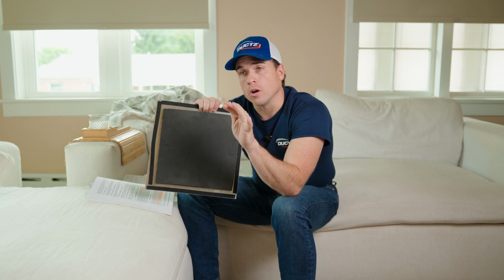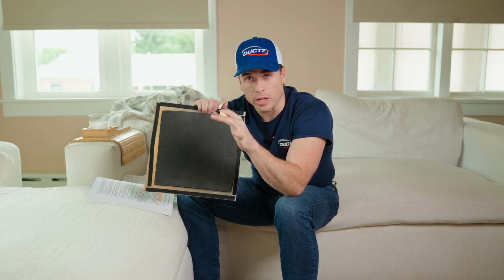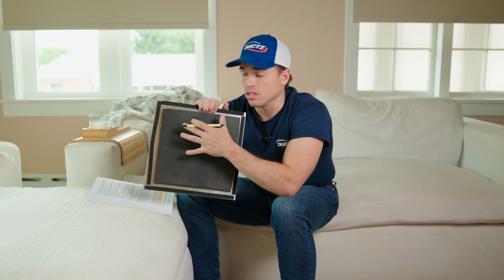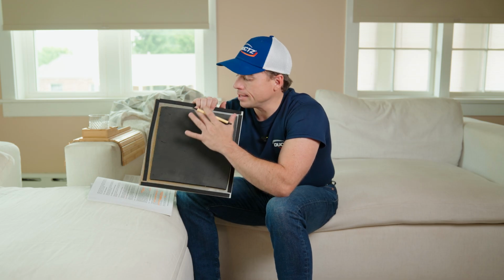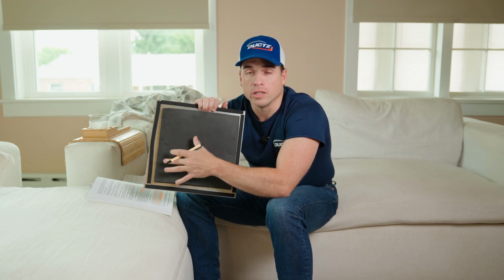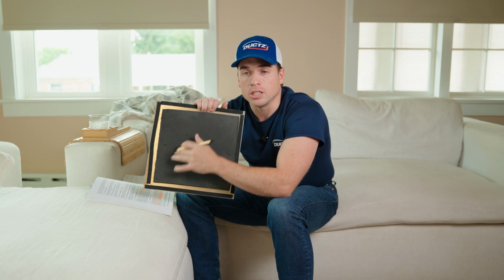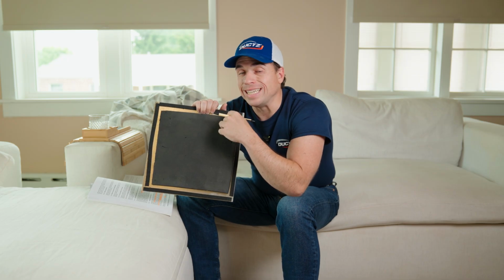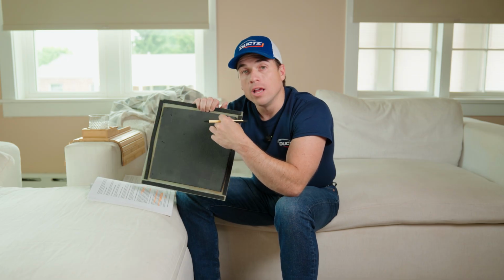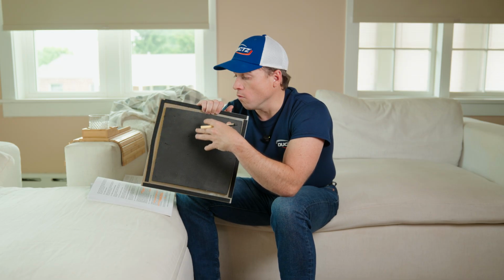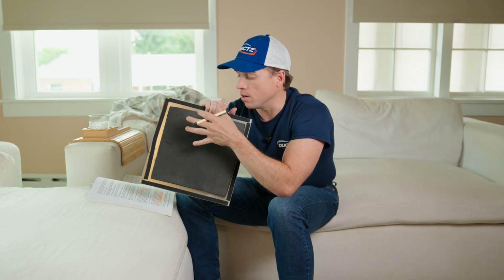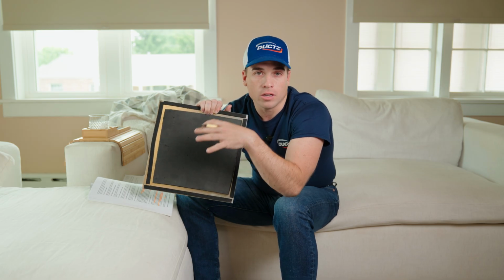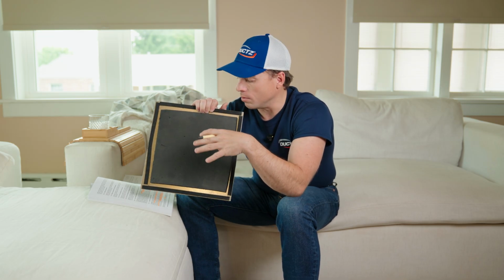Because when you are talking about adding a coating on this insulation, because let's say it's porous and after the fire, they're sitting there, you clean it out, you want to do the encapsulation. That encapsulation adds extra weight to the liner. If that extra weight overloads the glue and the glue is not strong enough, the liner will fall off and then fly down the duct, block the duct, cause all kinds of problems.